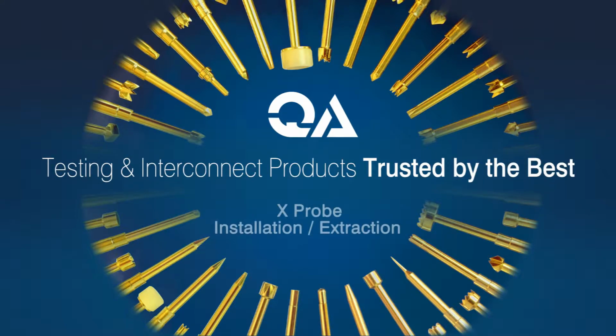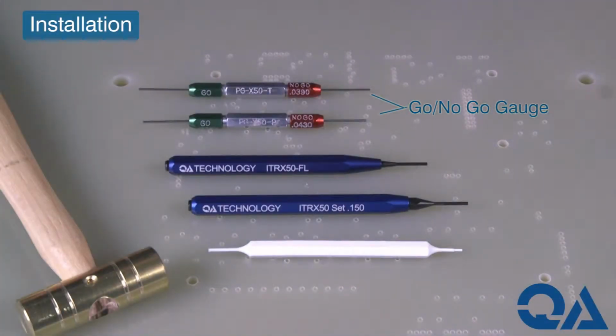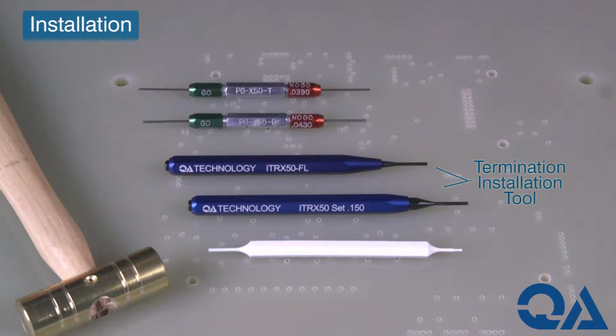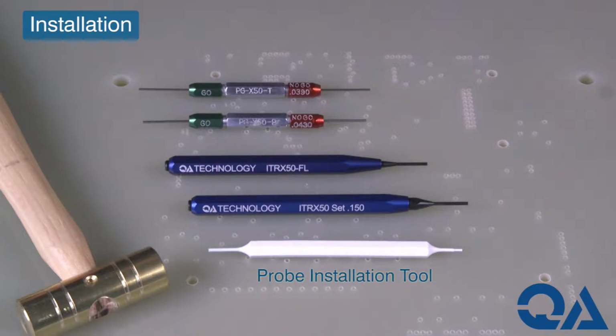To install QA XProbe termination pins to ensure best pointing accuracy, retention force, and overall performance, you'll need two go, no-go gauges to verify the hole size, a termination installation tool, and a hammer. To install the probe, you'll need a probe installation tool.